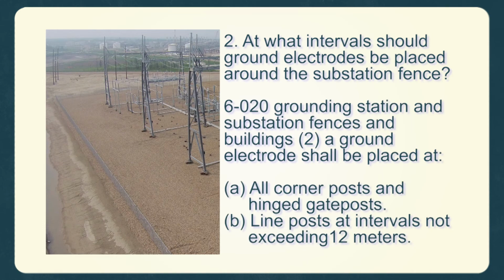6-020. Grounding station and substation fences and buildings. Number 2. A ground electrode shall be placed at A. All corner posts and hinged gate posts. B. Line posts at intervals not exceeding 12 meters.